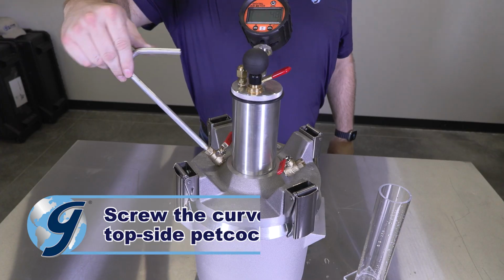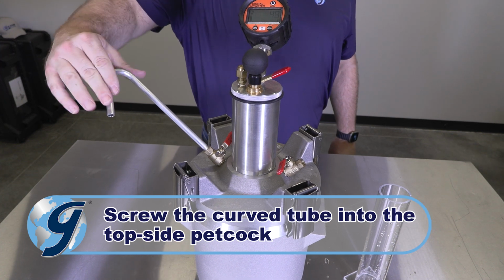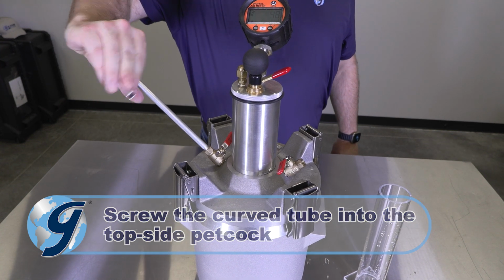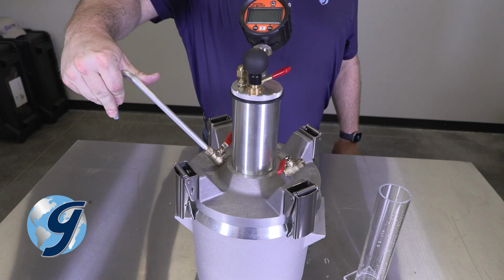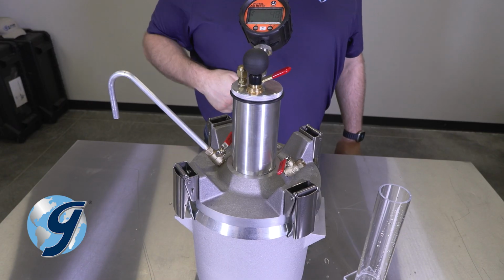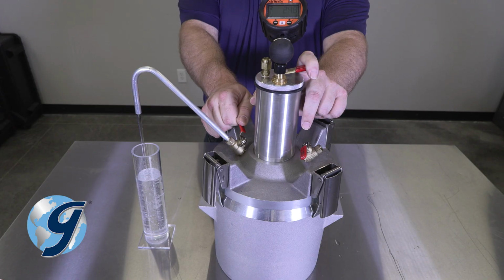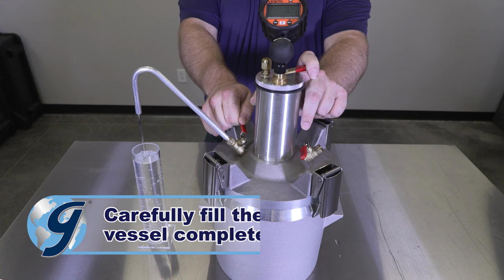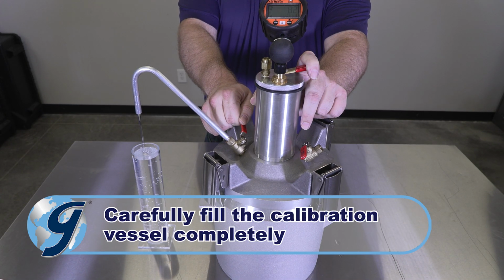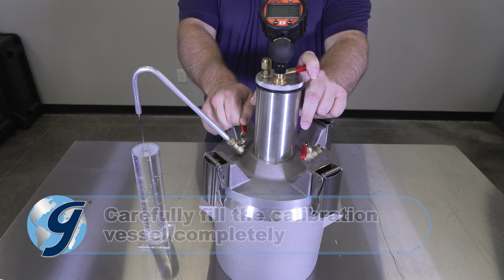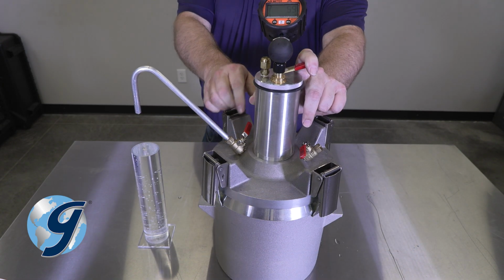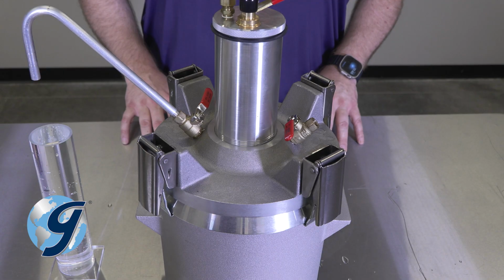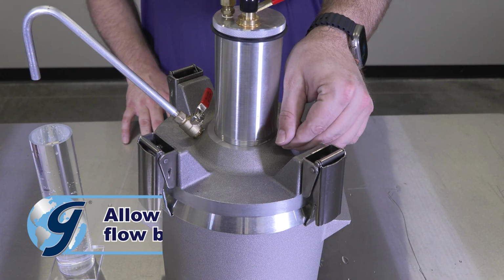Next, screw the curved tube into the topside petcock associated with the previously inserted bottom straight tube. Press the needle valve lever and hold it. Then, gradually open the petcock to control the flow. Carefully fill the calibration vessel completely. Do not overfill. Now, open the free petcock to release the pressure in the bowl.